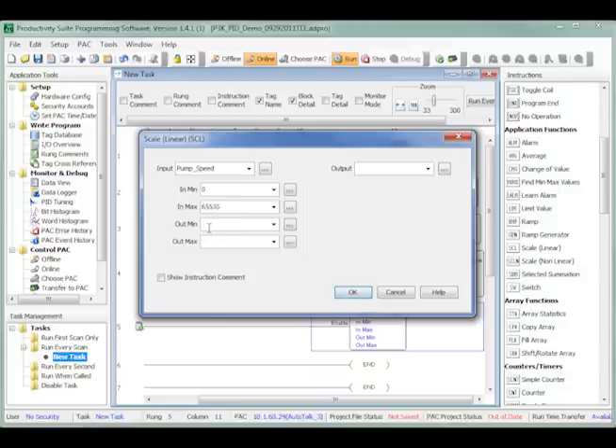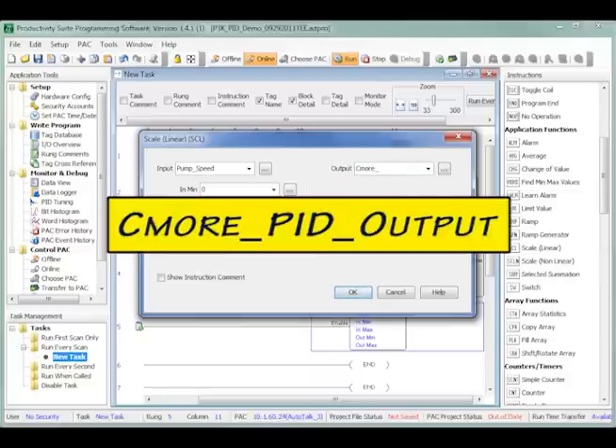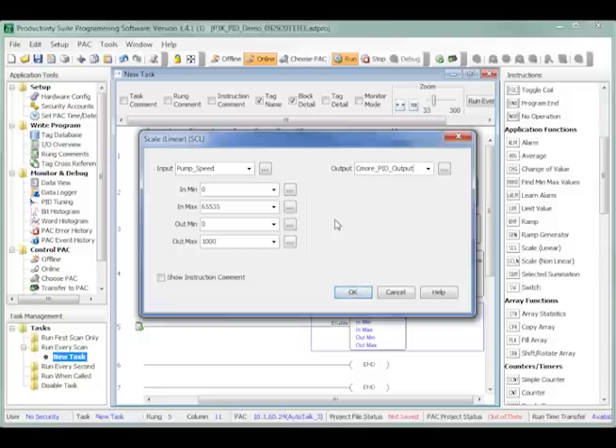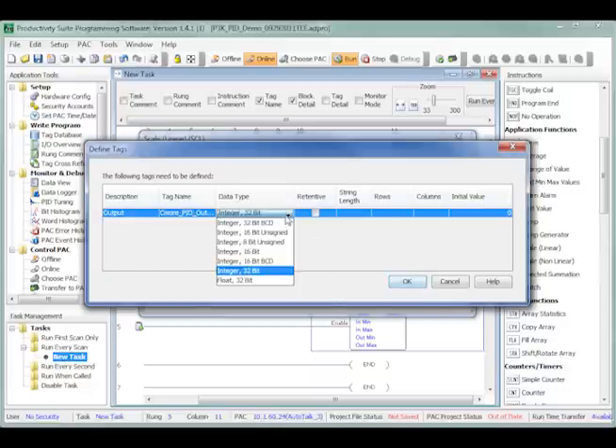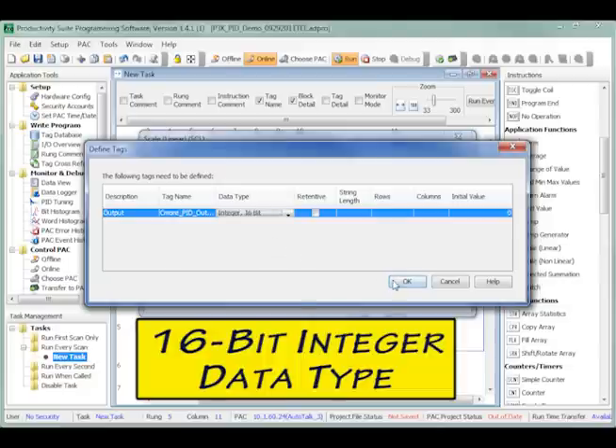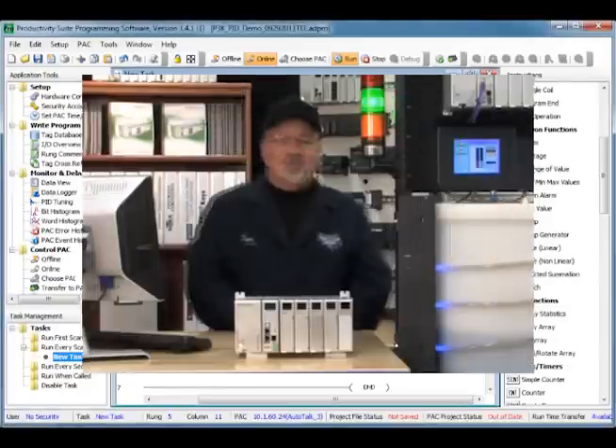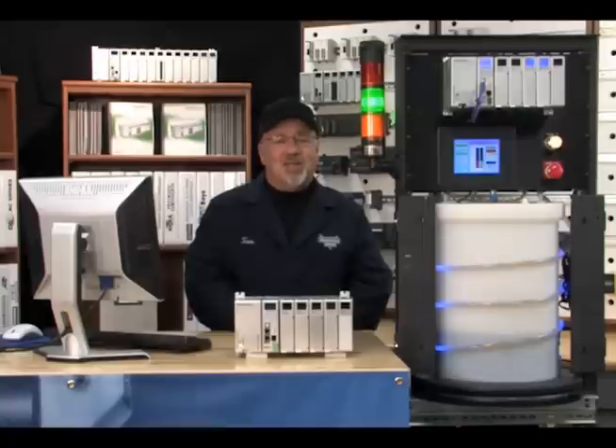To produce the 0 to 1,000 value to display on the C-more, enter 0 for the out min parameter and 1,000 for the out max. Enter C-more_PID_output in the output parameter then click OK. The define tags dialog box will come up in the programming software. I have assigned C-more_PID_output as an integer 16-bit data type. Follow along to part 7 as I get to the heart of this video series and explain the use of the Productivity 3000's PID loop instruction.